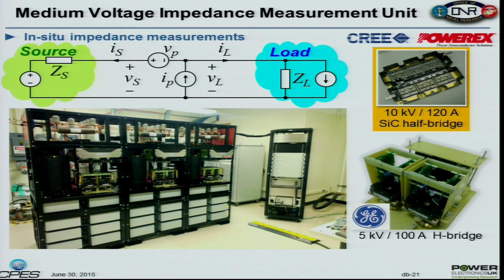This one was nice because we used 10 kV, 120 amp silicon carbide modules to switch at 20 kilohertz, so our injection bandwidth is much higher than the power transfer frequency, which is 60 hertz or so. That let us measure things up to the kilohertz range.